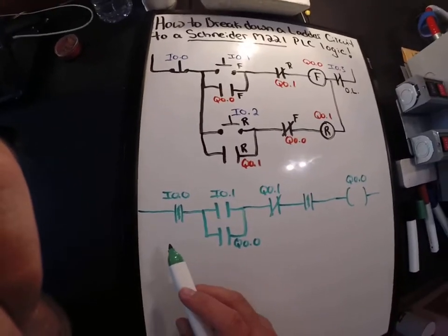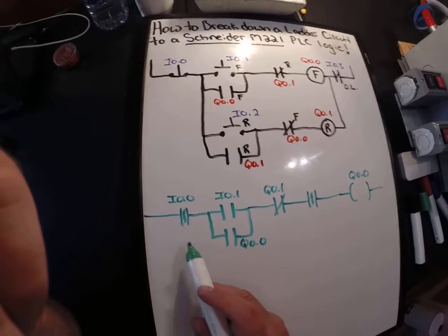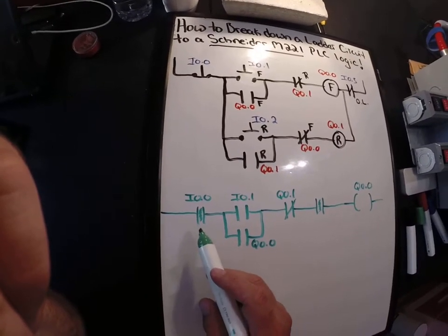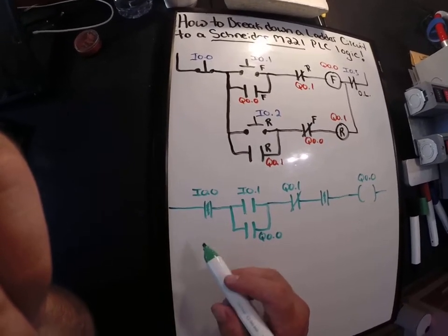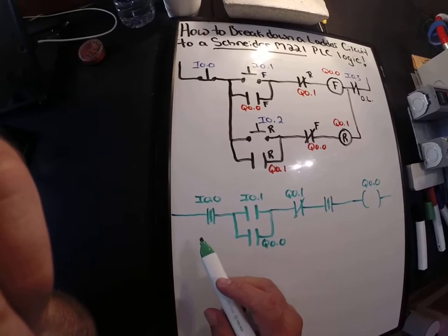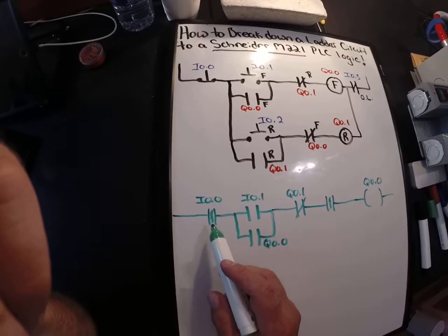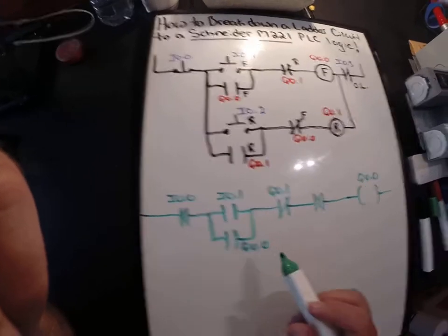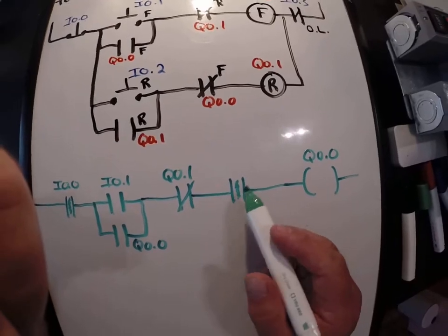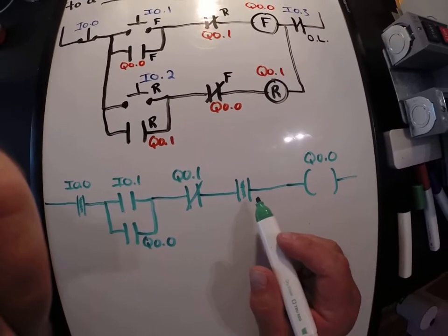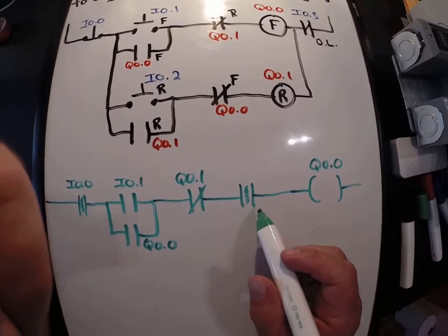I like that personally more than making the contact normally closed, because this shows the physical functionality of the button. So I know that once that cover is on, my stop is intact and I have a path for current flow here. Same thing with my single pole switch that I'm going to use to simulate my overload. I'm making that a normally open contact.